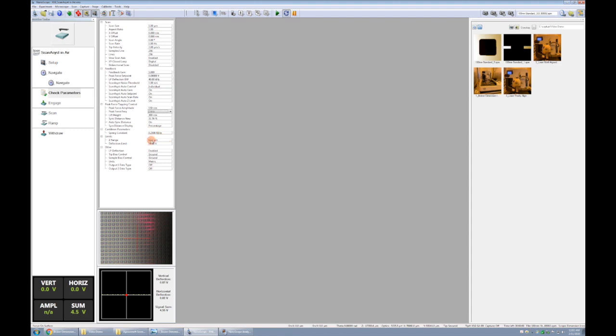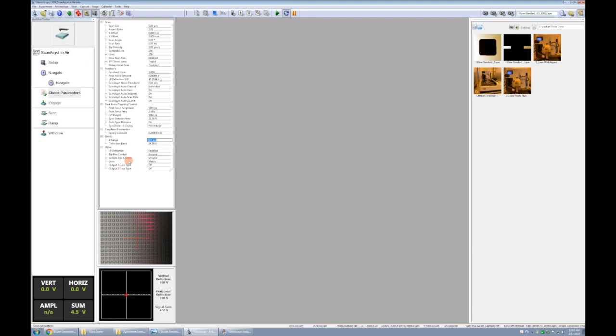Spring constant is just loaded in when we said we're using a scan assist probe from a lookup table. Z range is the total range that our piezo can travel, and right now we're allowing it to access the full 12 microns of that piezo. Down here are other things we can do. We can bias the tip, we can bias the stage. We're not going to do any of that in these videos. These are often used for other types of applications.